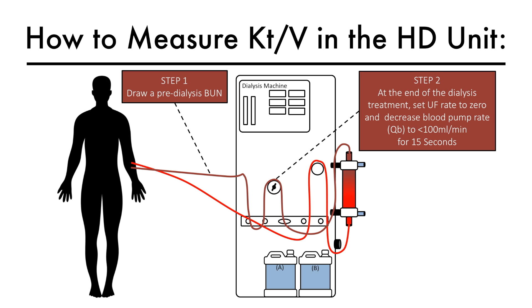Step 2, at the end of the dialysis treatment, slow the blood pump rate on the hemodialysis machine to less than 100 mL per minute for 15 seconds or so.